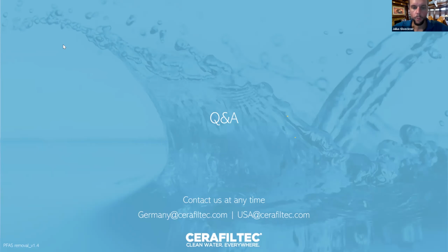And this only really works when you actually put the powder in a fixed bed configuration, right? From literature, we know, just as an example, if you dump a bunch of carbon in a contact tank, you get about 20% PFAS removal, right? So the magic is that you stack the powder activated carbon into a fixed bed to create the smallest contact angles to each other, or the contact spacing between the particles. And that allows for the highest removal effectiveness and efficiency.